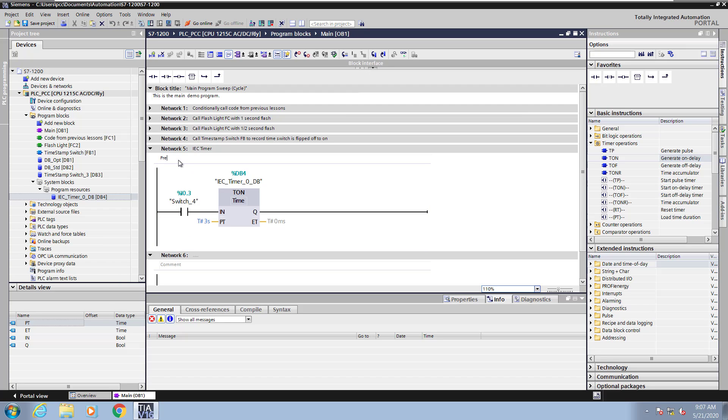Up in the comment area I will enter in some information on the format for the timer preset value. So you can enter in a preset value with a number of different durations. So you can do things like t pound 1d for 1 day, 2h for 2 hours, 3m for 3 minutes.